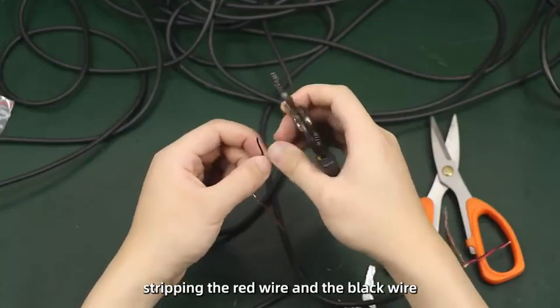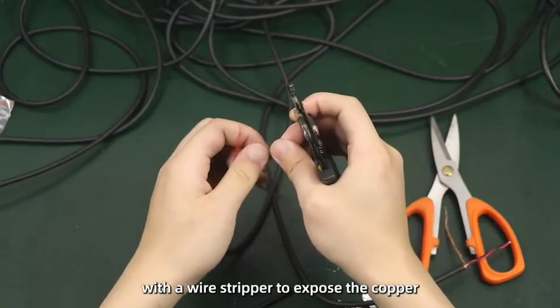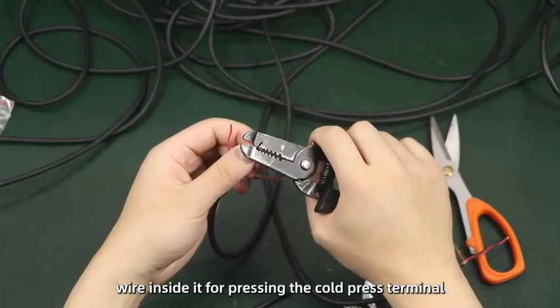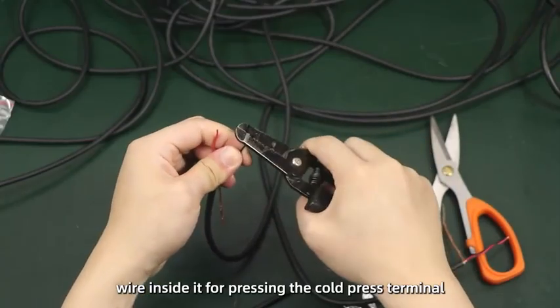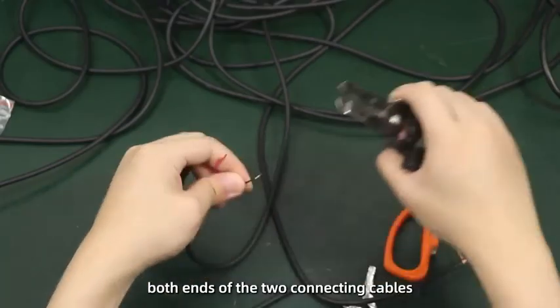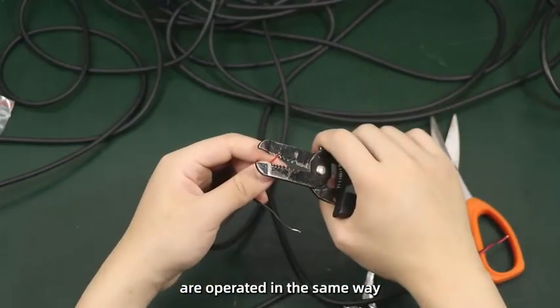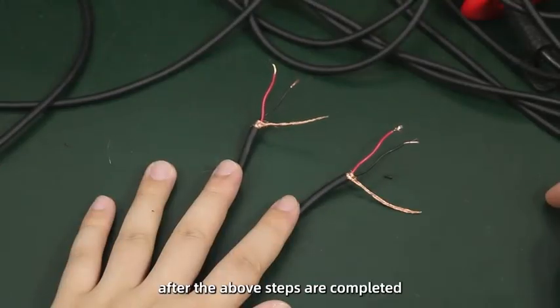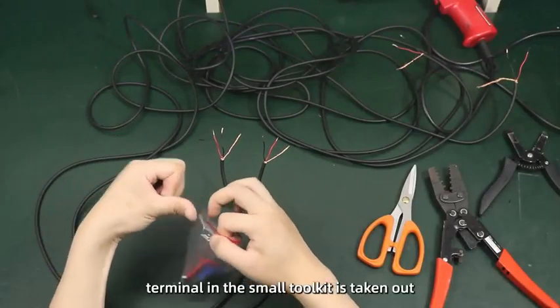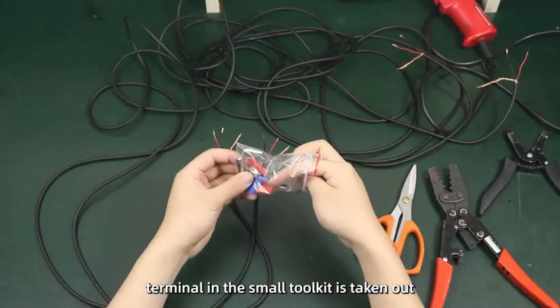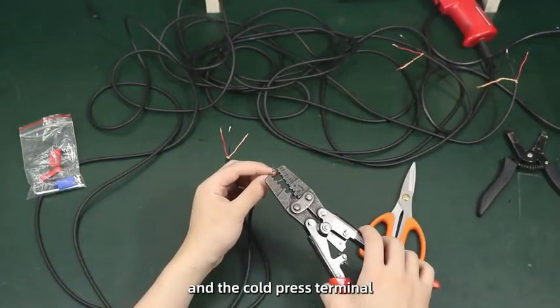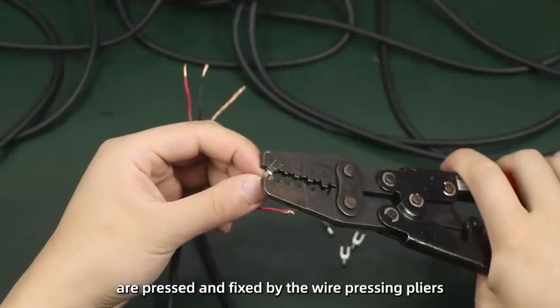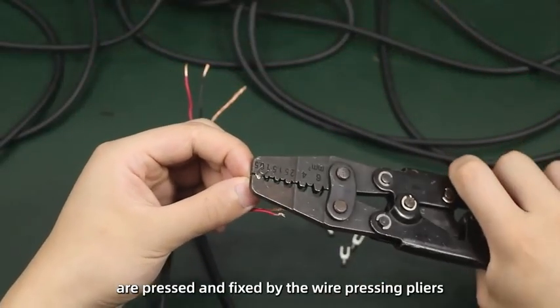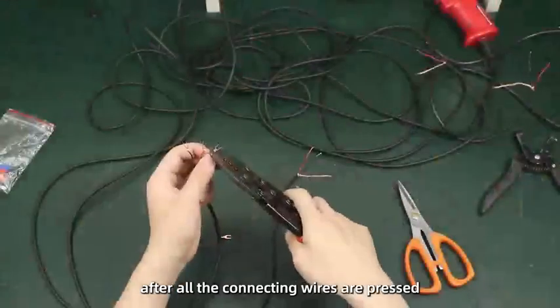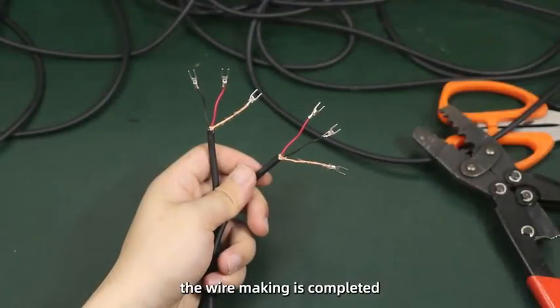Strip the red wire and the black wire with a wire stripper to expose the copper wire inside for pressing the cold press terminal. Both ends of the 2 connecting cables are operated in the same way. After the above steps are completed, the cold press terminal in the small toolkit is taken out, and each connecting wire and the cold press terminal are pressed and fixed by the wire pressing pliers. After all the connecting wires are pressed, the wire making is completed.